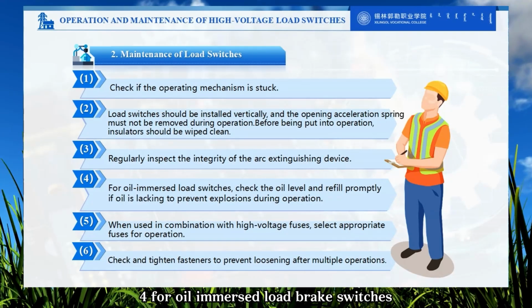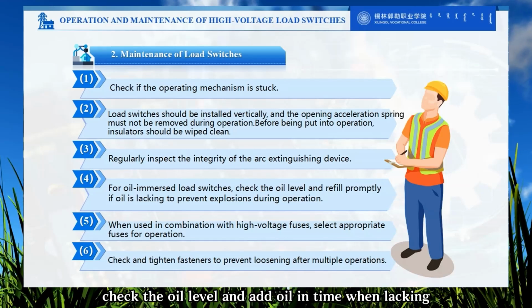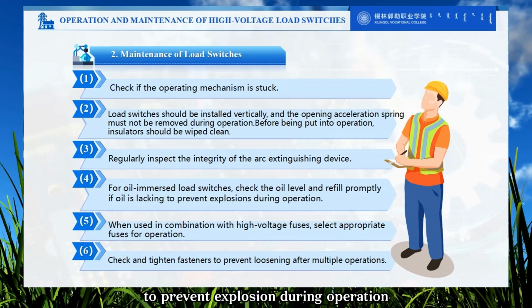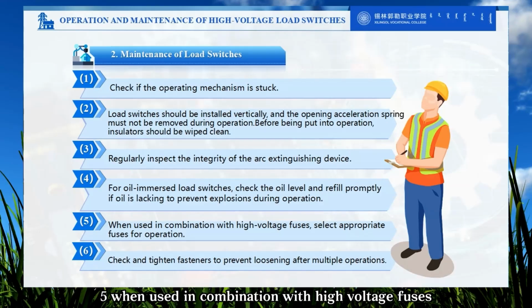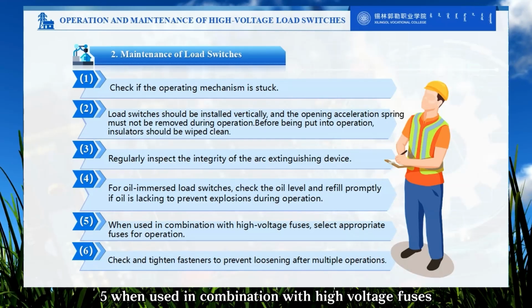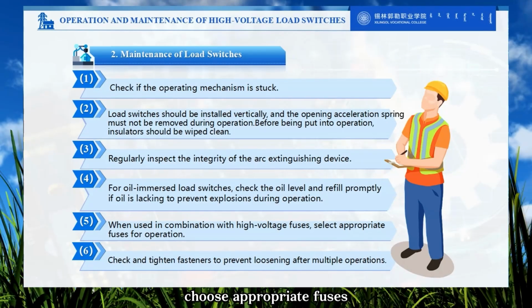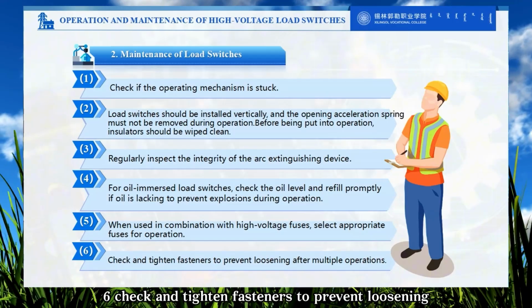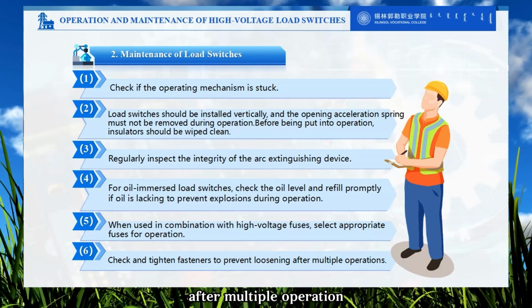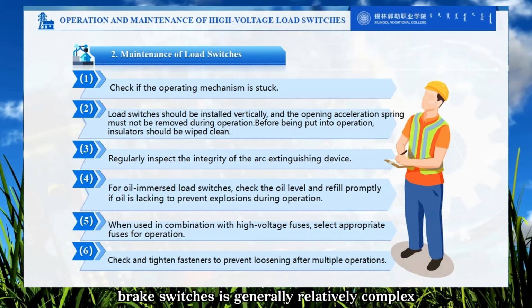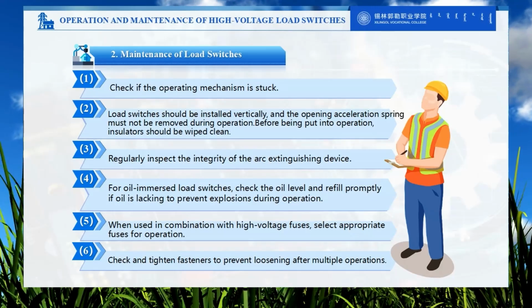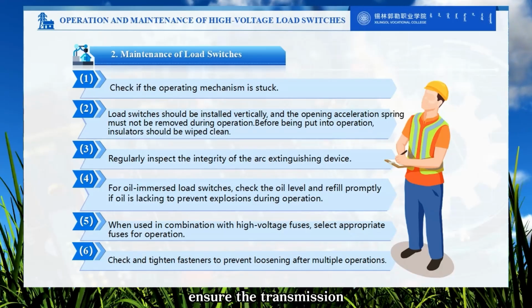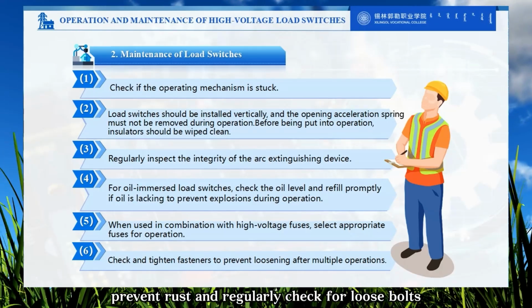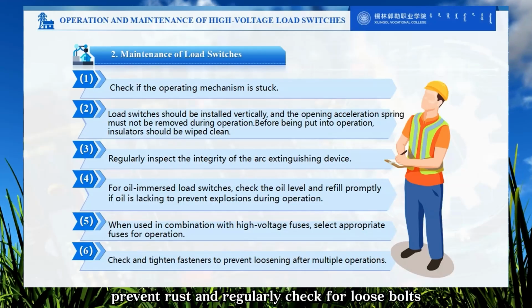4. For oil-immersed load break switches, check the oil level and add oil in time when lacking to prevent explosion during operation. 5. When used in combination with high-voltage fuses, choose appropriate fuses. 6. Check and tighten fasteners to prevent loosening after multiple operations. The operation of load break switches is generally relatively complex. During operation, ensure the transmission components are in good condition, prevent rust, and regularly check for loose bolts.